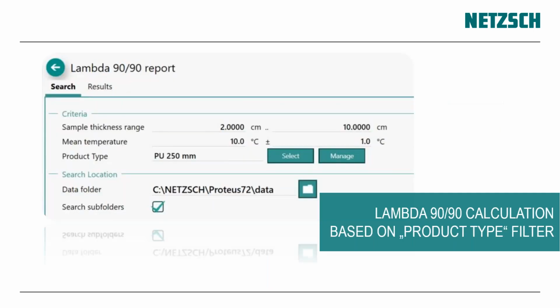And the Lambda 9090 calculation is based on the product type filter. So every time you have a sample of, let's say, 25 millimeters, but you use it for polyurethane 100 millimeters, polyurethane 250 millimeters, you can do a really product type related Lambda 9090 report at a mouse click. And this is really efficient.